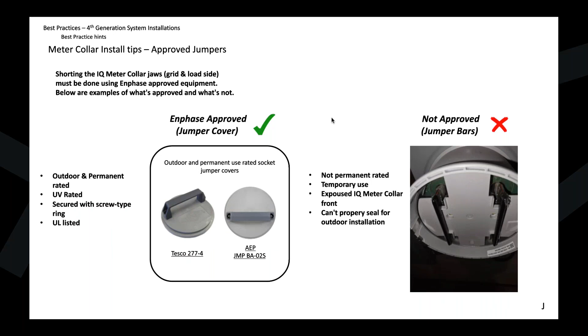And what we've seen is these jumper bars over here on the right with the red X, that's just going to be a kind of temporary solution. When you're testing, doing MPUs, doing swaps on some utility equipment, you could use those to simply short those and do some tests, but they're not meant for permanent use like those jumper covers are. Also with these bars, you don't have a way to really seal up that collar, which is obviously going to compromise the NEMA 3R rating. So again, learning here is use one of the approved jumper covers and do not use these jumper bars.